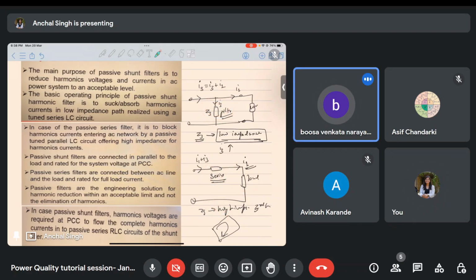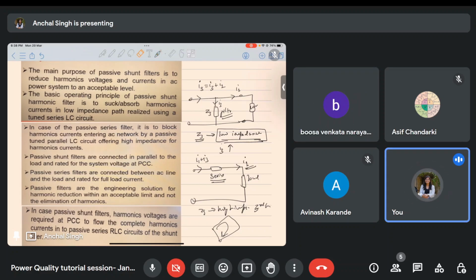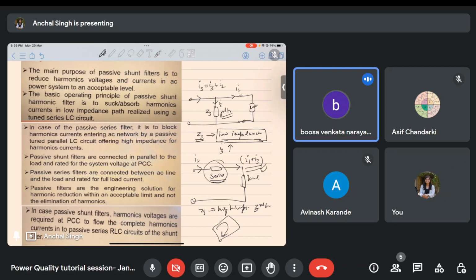Madam, what about this I3 component, will it reflect on the supply or will it be stored in the filter? I need some clarity, madam. This I3 component also has some energy. Okay, sorry, this should be like this. My load wants both I1 plus I3, and my source will be given only I1. It is actually preventing the source side from sourcing this third harmonic component. The load will still need it, and this third harmonic component will be supplied by this series filter. There will be a capacitor branch which will source this reactive power current. Okay.